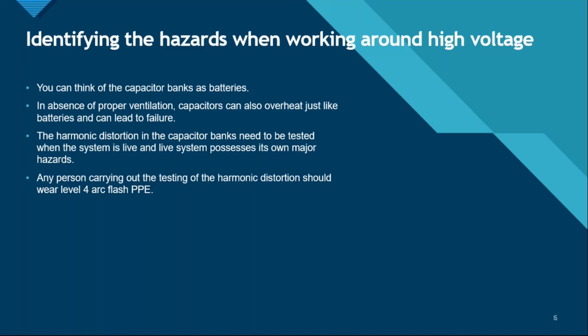All right, because there is always a high amount of electricity flowing through capacitor banks, and for checking the harmonic distortion there are different testing devices. The person carrying out the testing needs to put their hands in the area of danger, and if by chance he touches the electrical cable, there might be a major case of electrocution. So they should always have level 4 arc flash PPE on them.